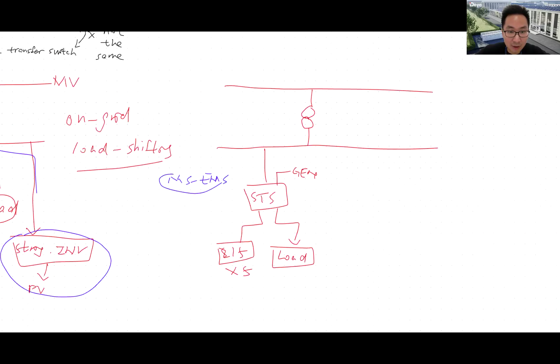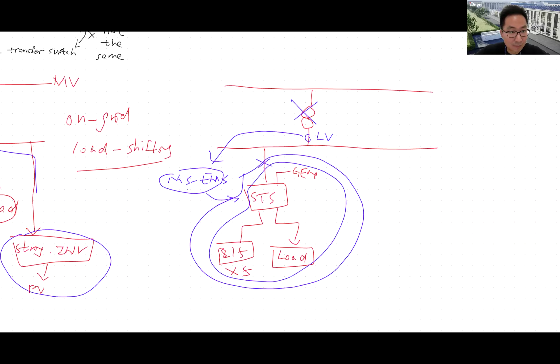It's working as a small system. The moment the grid goes out, the STS will cut the grid side relay, and all of this is operating within its self-contained small system controlled by this EMS. And you can multiply this. I'm not too familiar with this platform just yet. You can multiply this indefinitely as long as you have enough budget and enough capacity left in the transformer, basically. So all this is a self-contained system when the grid is gone. And yeah, those are 2 of the most commonly asked operations.